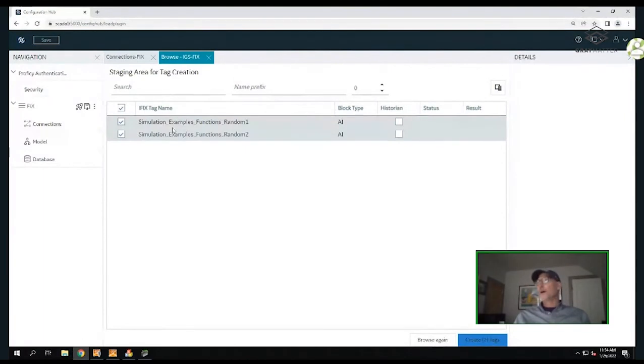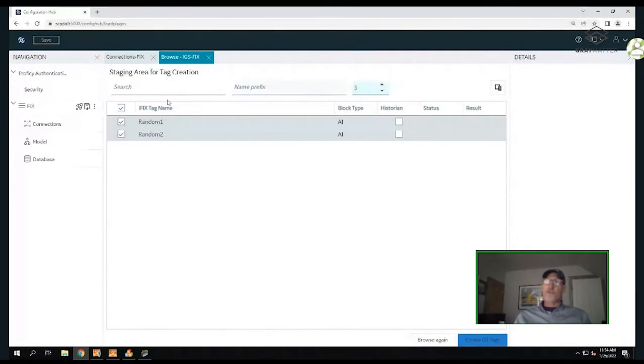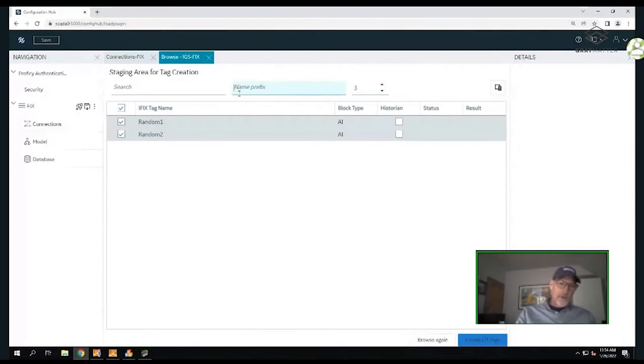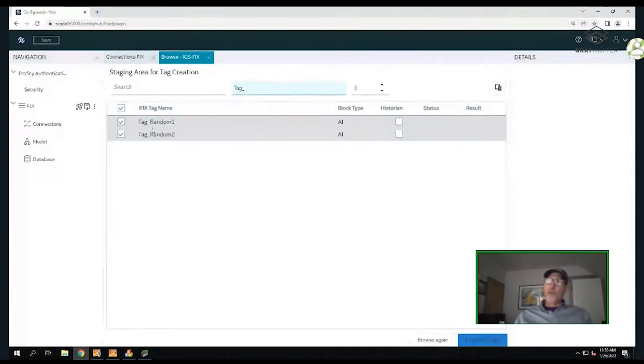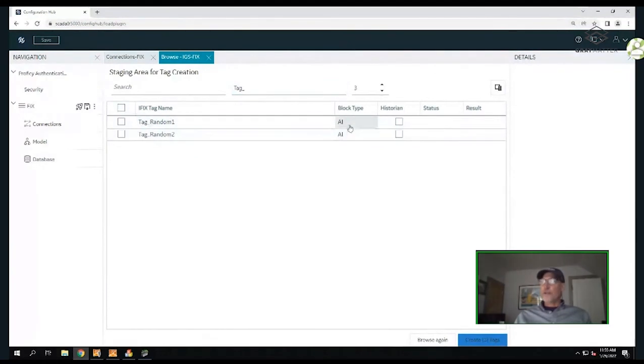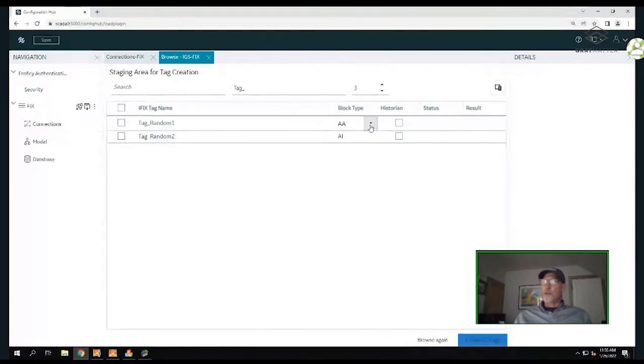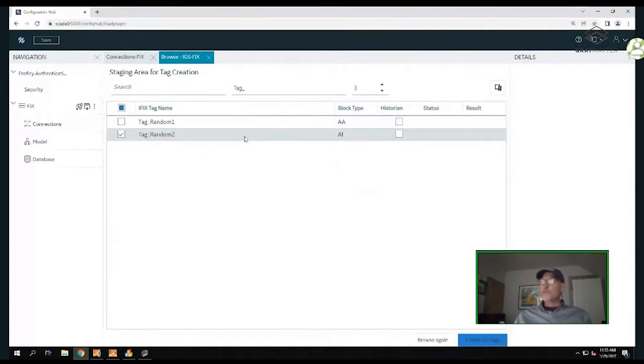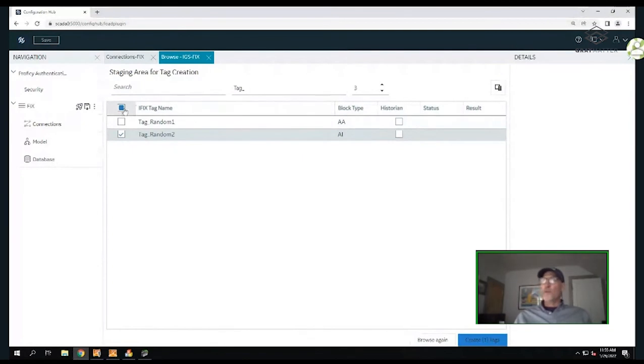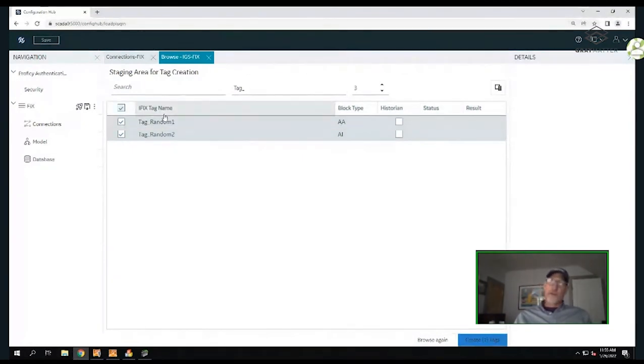You can go with the format the IGS already has, or maybe it's a bit messy - here's a chance to clean that up by trimming the tag name down. You can add a prefix - put your tag name or site name - and it will build out that structure for you. You can also select the type: make it an analog alarm tag or a discrete tag. You can also choose to historize the tag, automatically routing it to the historian.